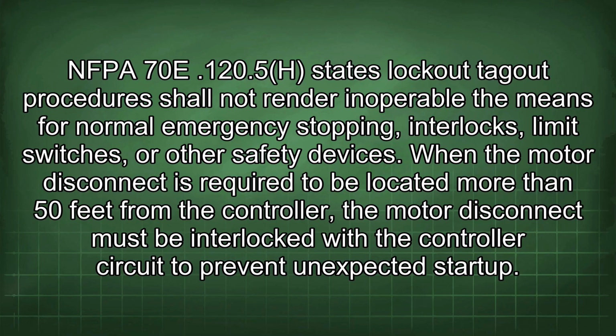NFPA 70E .120.5(H) states lockout tagout procedure shall not render inoperable the means for normal emergency stopping, interlocks, limit switches, or other safety devices. When the motor disconnect is required to be located more than 50 feet from the controller, the motor disconnect must be interlocked with the controller circuit to prevent unexpected startup.